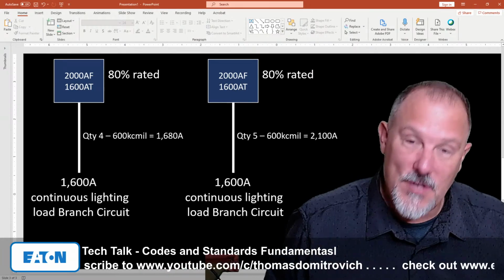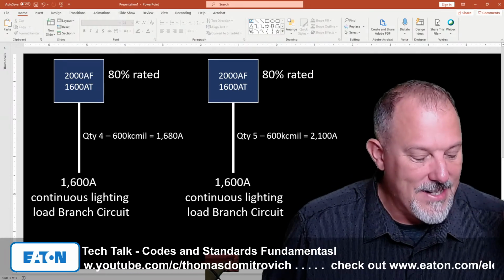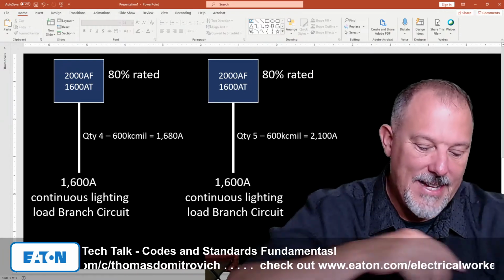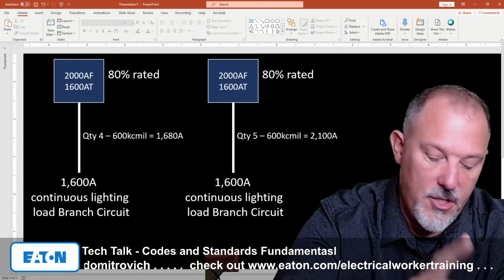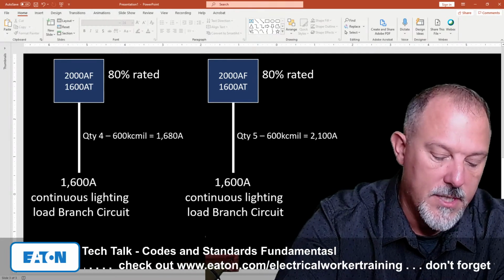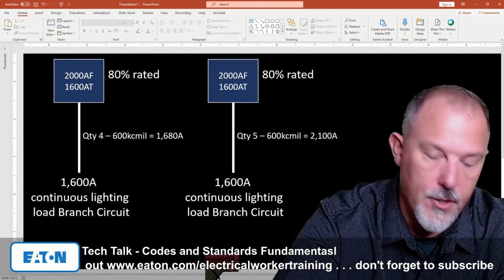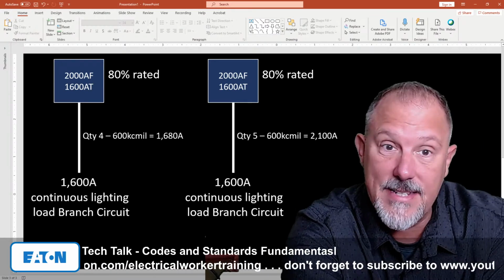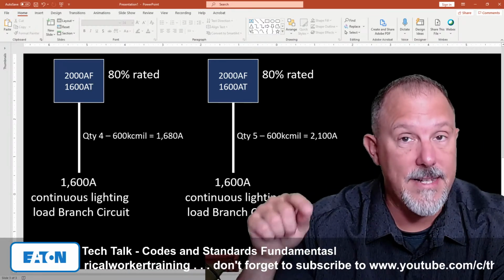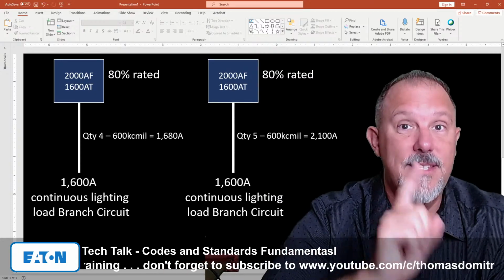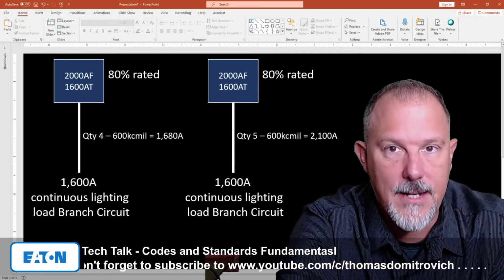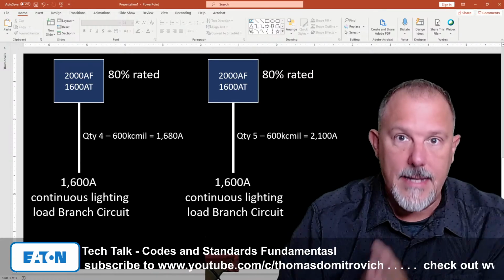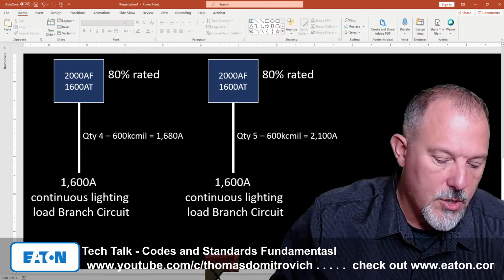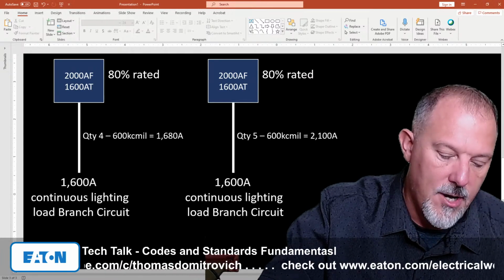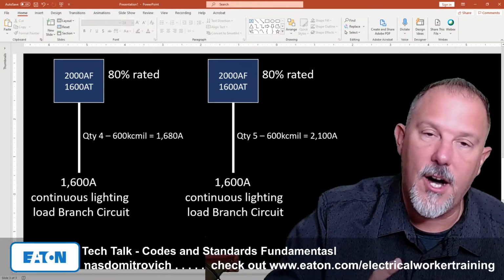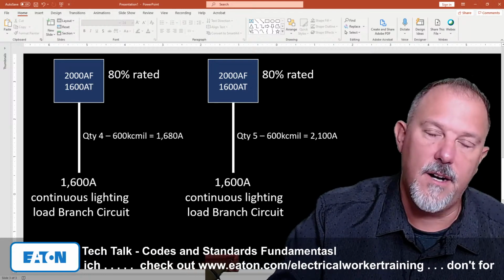So let's go back to 210. If I go to 210.20(A), it says, where a branch circuit supplies continuous loads or any combination of continuous and non-continuous loads, the rating of the overcurrent device, which now is 1600 amps, remember, because 240.6 with the locked cover says that I can adjust it to 1600 amps, and now its rating is 1600 amps. So that 1600 amp rating shall not be less than the non-continuous plus 125% of the continuous loads.